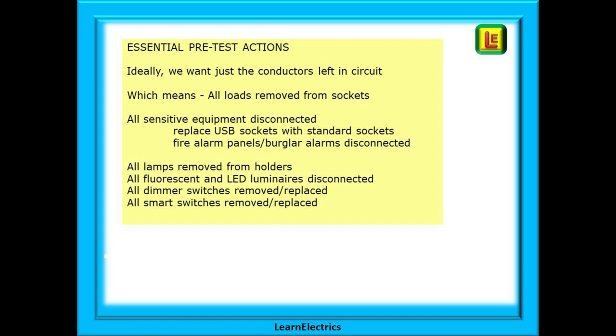All loads must be removed from sockets. All sensitive equipment must be disconnected. A 500 volt test voltage will damage some devices. Replace USB charging sockets with standard sockets, and fire alarm panels, burglar alarms and similar should be disconnected. All lamps must be removed from their holders. All fluorescent and LED luminaires must be disconnected as these contain transformers that will indicate a fault and may also be damaged by the testing. All dimmer switches should be removed and all smart switches removed too. For the duration of the tests, replace them with standard switches.